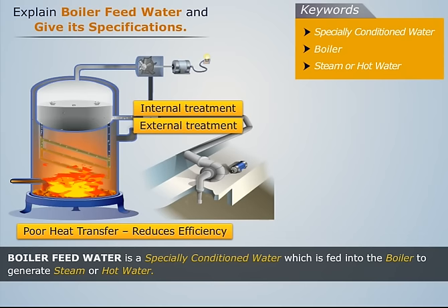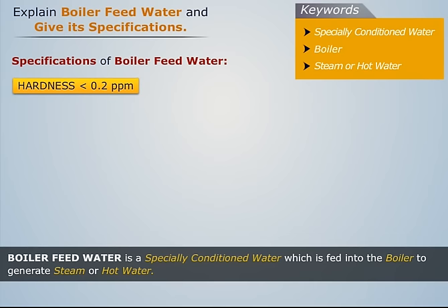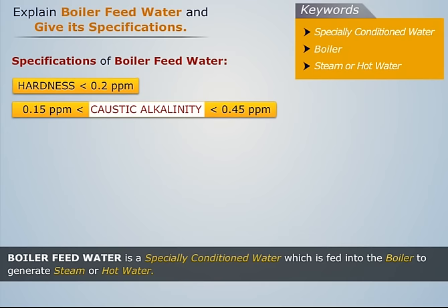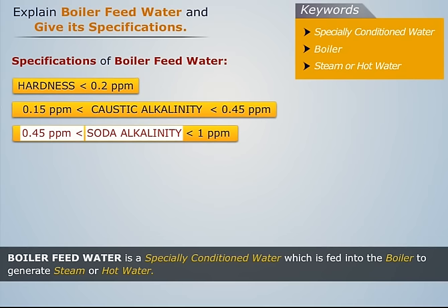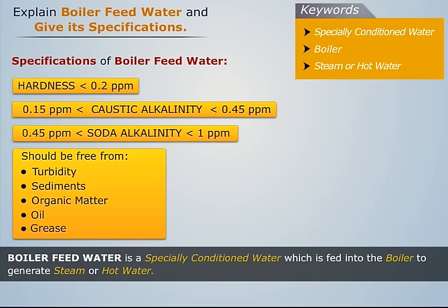Let us now discuss the specifications of boiler feed water. Before using the boiler feed water in the boiler, it should be ensured that it meets the following specifications: its hardness should be below 0.2 parts per million; its caustic alkalinity should be between 0.15 and 0.45 parts per million; its soda alkalinity should be between 0.45 and 1 parts per million; it should be free from turbidity and sediments; and it should be free from organic matter, oil, and grease to avoid foaming.